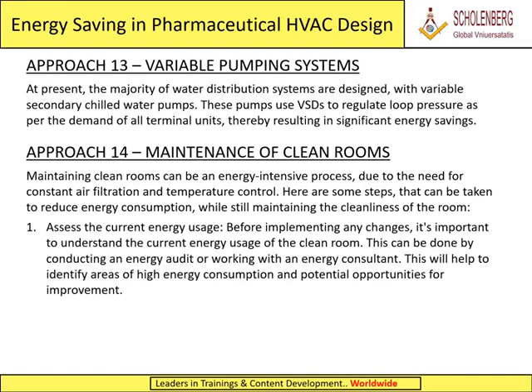Approach 14, Maintenance of clean rooms. Maintaining clean rooms can be an energy-intensive process, due to the need for constant air filtration and temperature control. Here are some steps that can be taken to reduce energy consumption, while still maintaining the cleanliness of the room. 1. Assess the current energy usage. Before implementing any changes, it's important to understand the current energy usage of the clean room. This can be done by conducting an energy audit or working with an energy consultant. This will help to identify areas of high energy consumption and potential opportunities for improvement.